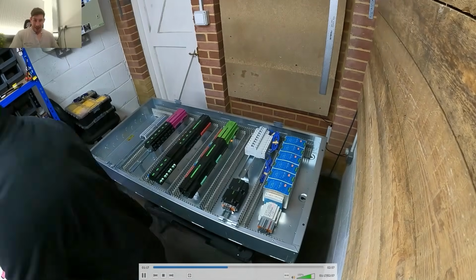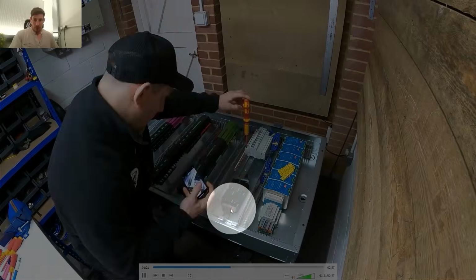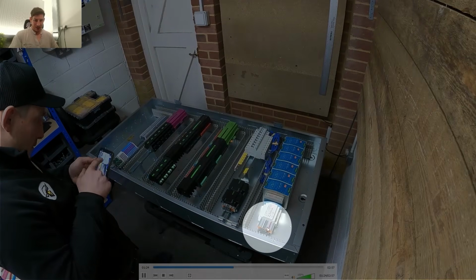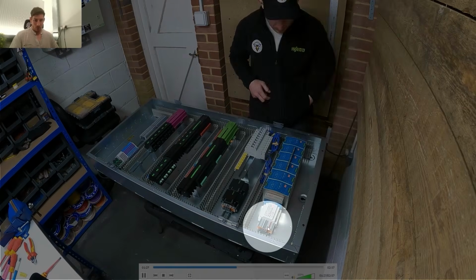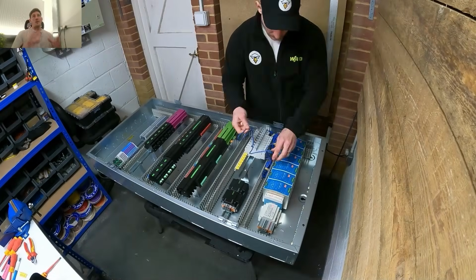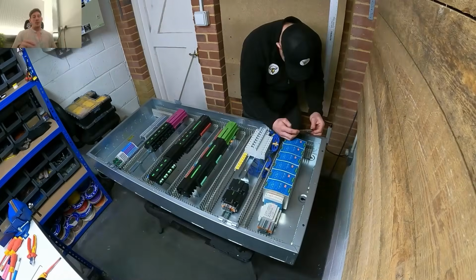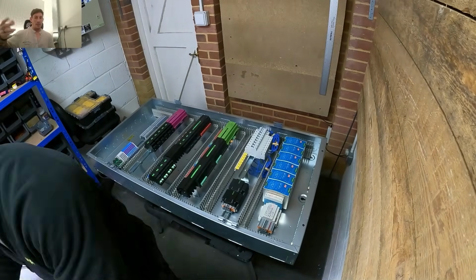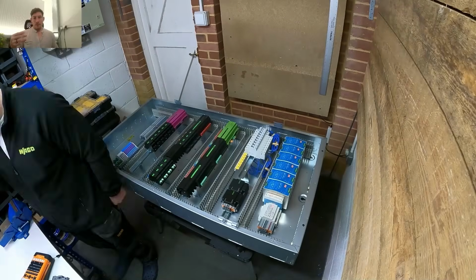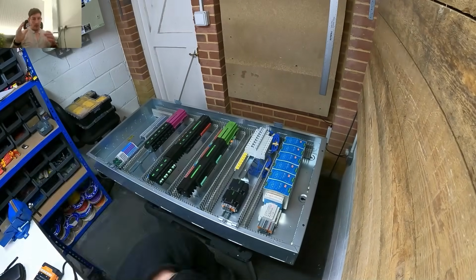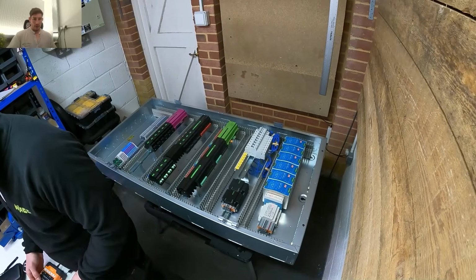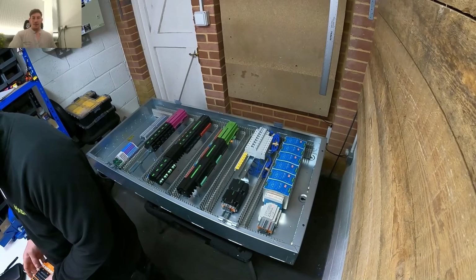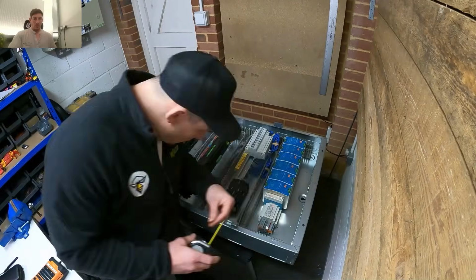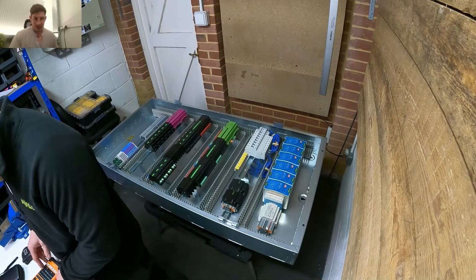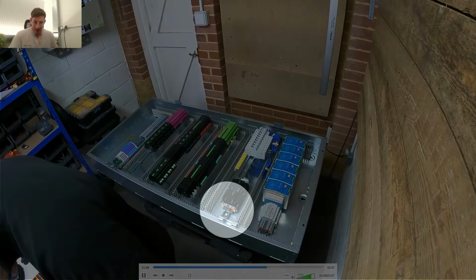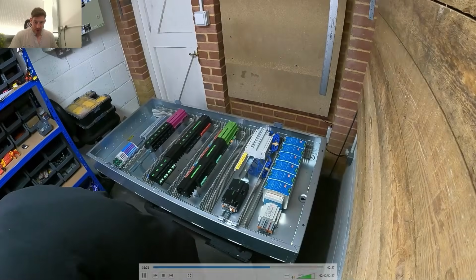What you're seeing me add here is fused terminal blocks. We still want to be fusing, even though it's 24-volt DC, to protect the outbound cables. If there's an overcurrent, the fuse will blow and it's all safe, so we don't just do that for mains voltage 230-volt AC, we also want to do that for any DC voltages as well. I later change where these fused terminal blocks are and move them up.